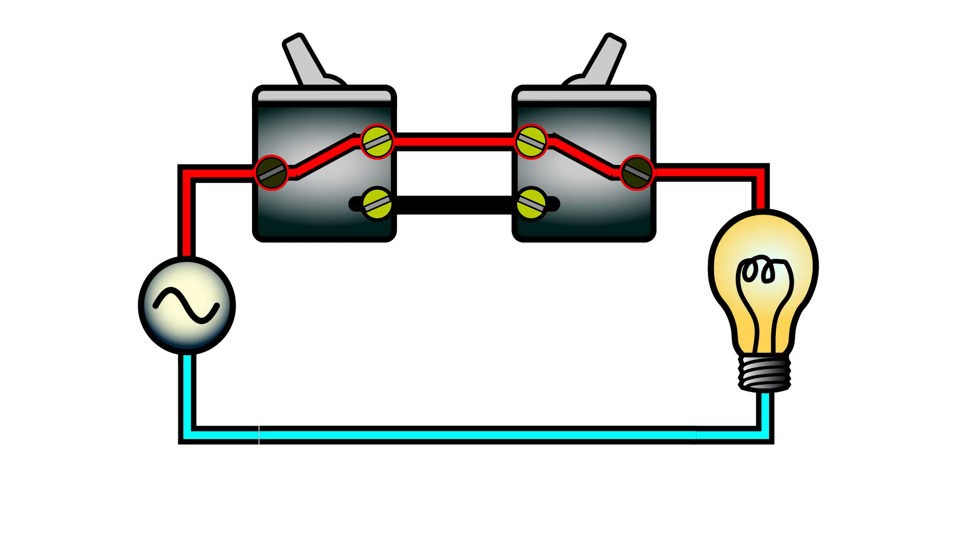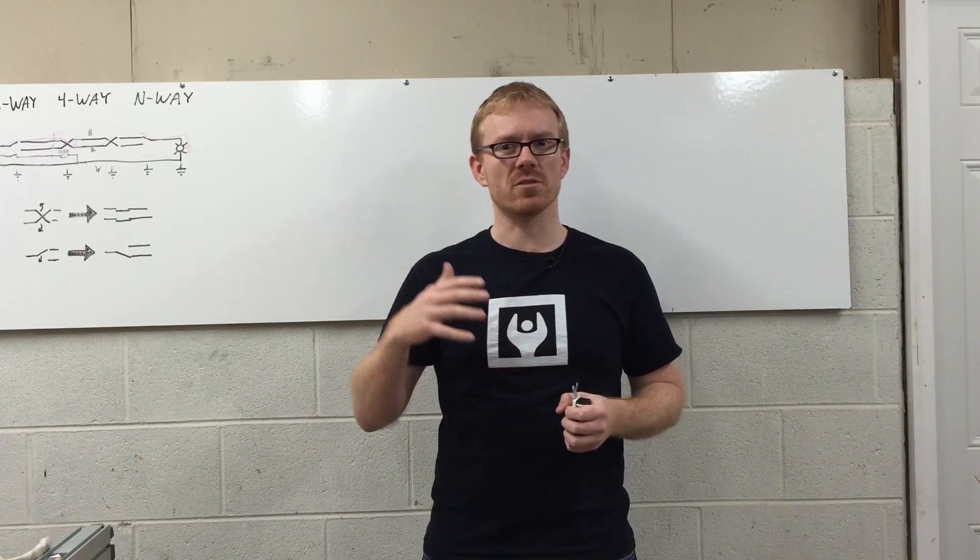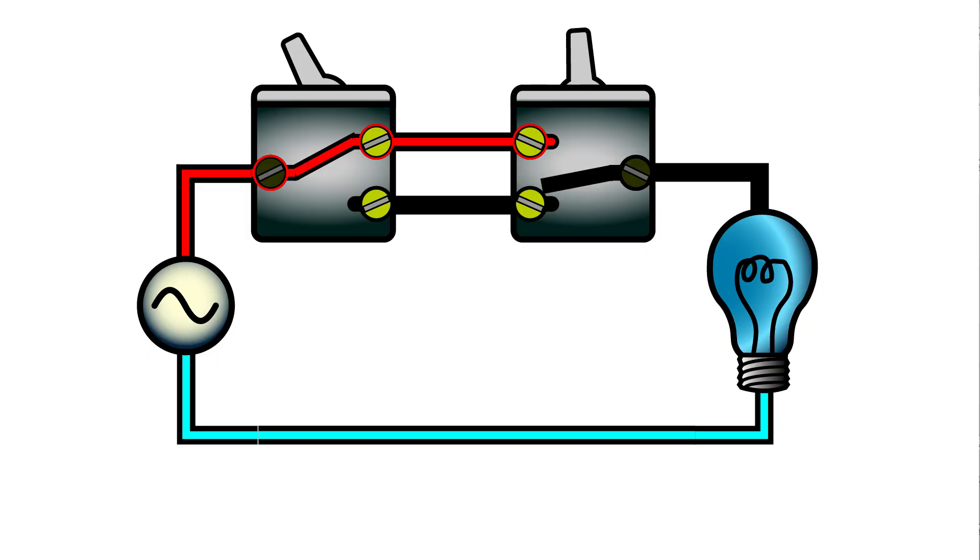When the first switch is toggled, the top traveler is energized. When the second switch is toggled, the energized traveler, or the unenergized traveler, is switched on to the source side of the load. Depending on which traveler is connected to the load, it'll either be turned on or off. Either switch can be used to control the load.